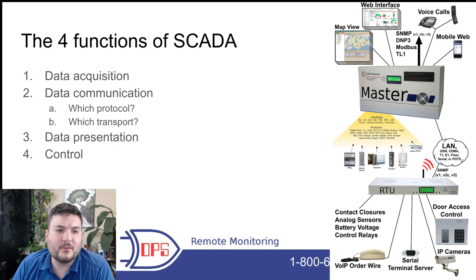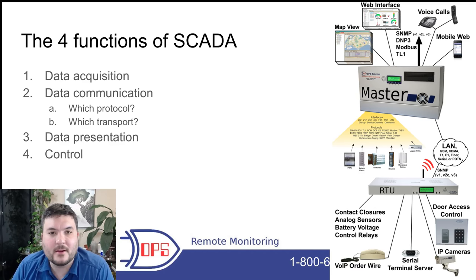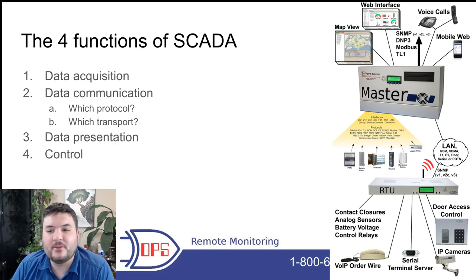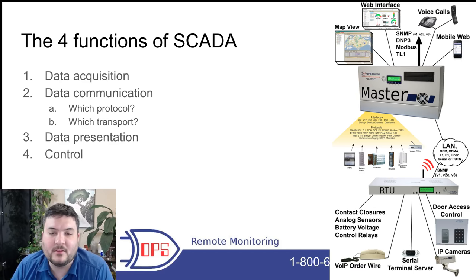SCADA basically falls into four basic functions. Looking at the diagram, data acquisition is the first one — in the lower portion where the RTU is, a collector device that pulls in contact closures, sensor data, and protocol data. Then there's data communication: once you've collected that data, it's got to go somewhere. If you have many RTUs in different locations, that revolves around the protocol the RTU uses and the transport — whether network, cellular, or even satellite — to talk back to the central collector, which we call the master or HMI.